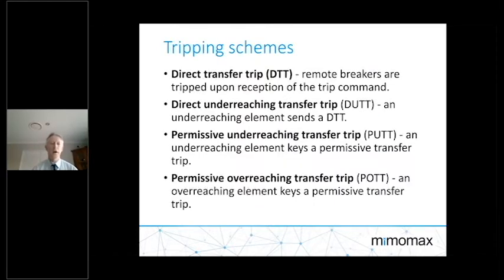So tripping schemes, there are a number that people in the industry will know much more about than I do, but to just highlight a few of them: direct transfer trip, and they are related to breakers that are tripped upon reception of the trip command. Underreaching transfer trip, an underreaching element sends the direct transfer trip, and the underreaching refers to where that element sits in the electrical grid. So is it at the remote end or at the source end or the base end? So we were saying underreaching, it is not at the far end, it is at the base end or the source end, and overreaching refers to where we're starting to sample at the far end or the remote end.